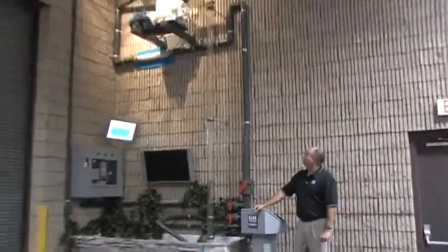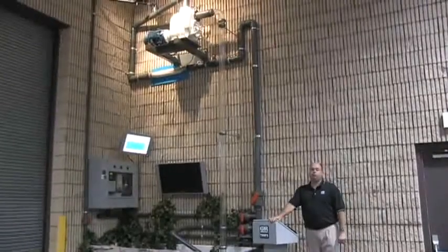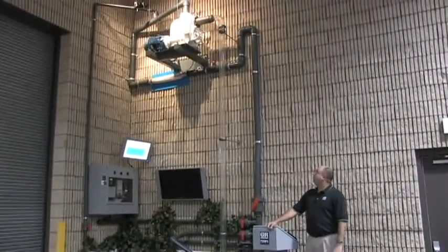In this portion of the demonstration, we want to talk about the priming capability of the pump. Right now we've got the pump on a 15-foot suction lift, and we do not have any check valves in the system, no check valves on the suction side, and no check valves on the discharge side.